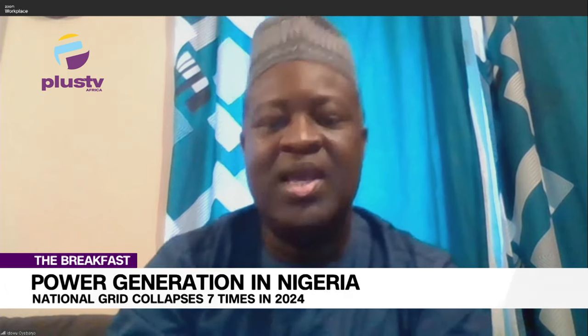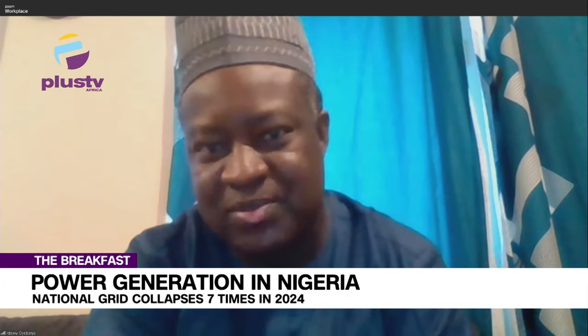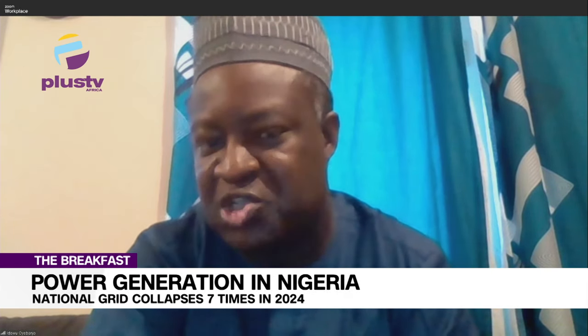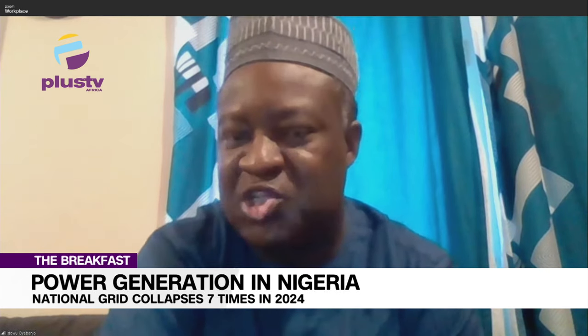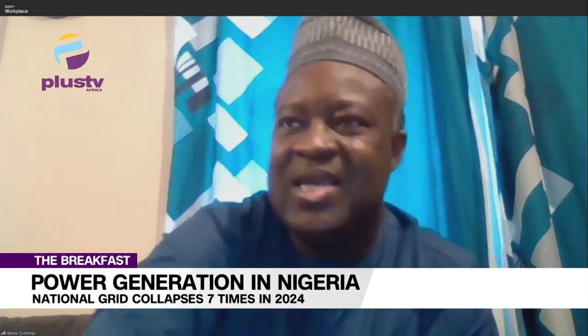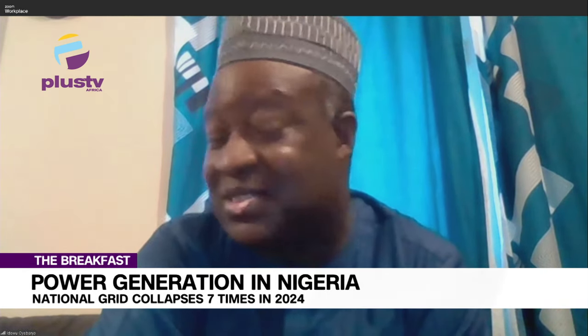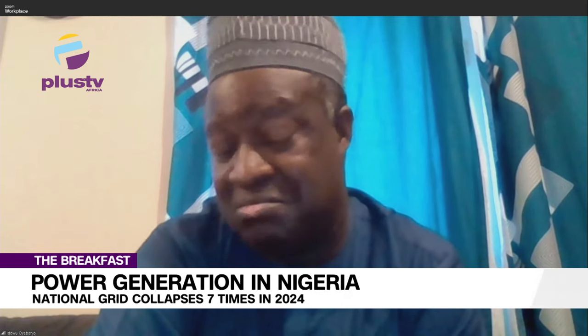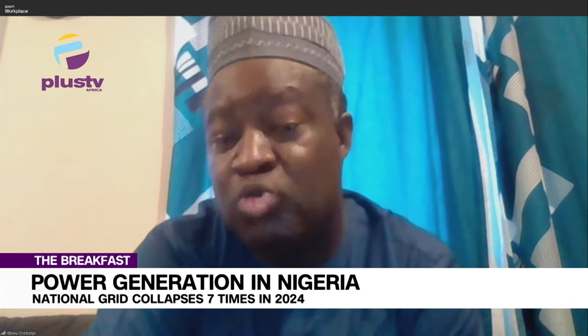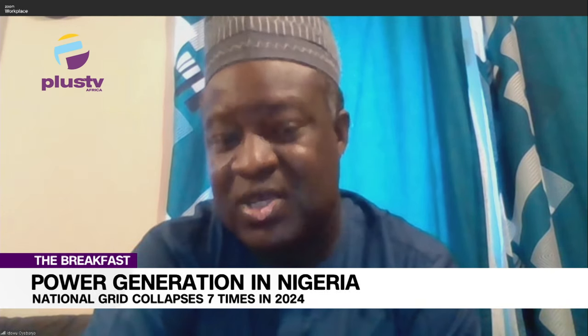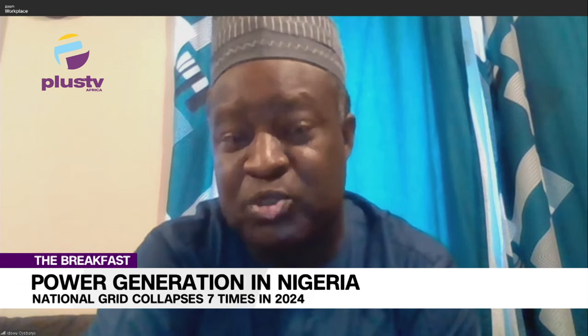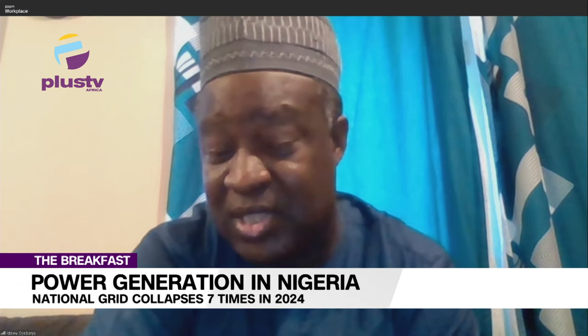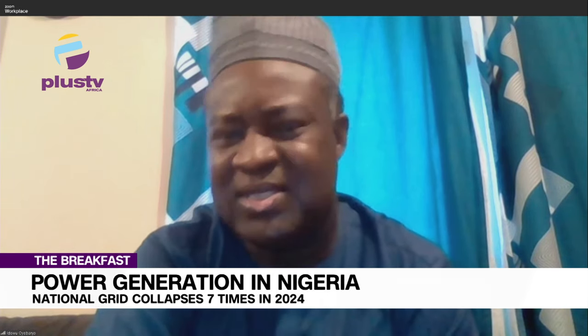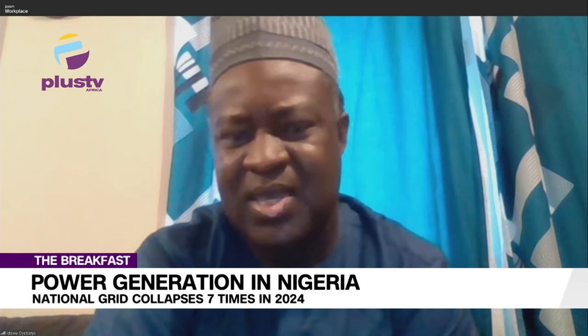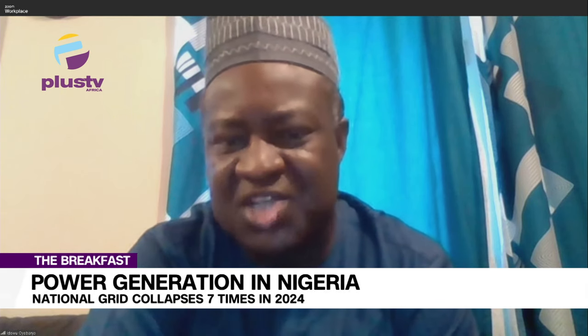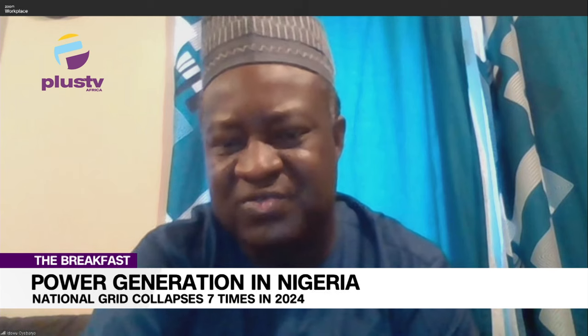Another thing that affects grid collapse, shamefully, is the lack of protection coordination. This is a big problem in Nigeria. The system is not coordinated, so it will never be stable. It will always go into grid collapse unless we decentralize and put protection coordination in place as an important tool. There are other things that can cause grid collapse too—essentially, load rejection can cause it. All of these factors put together cause us problems.